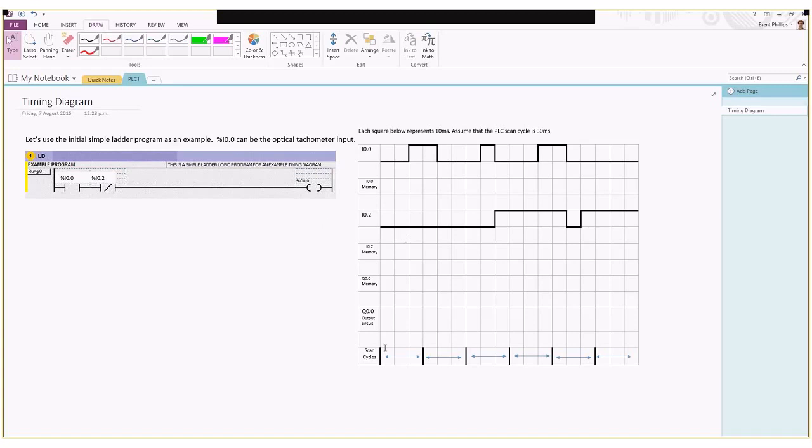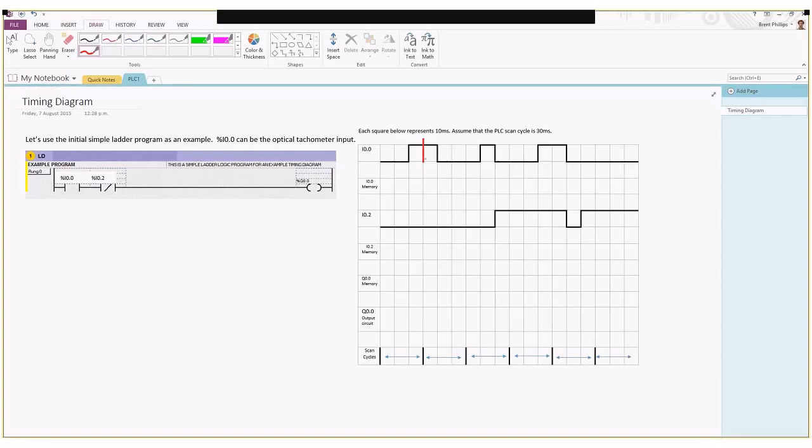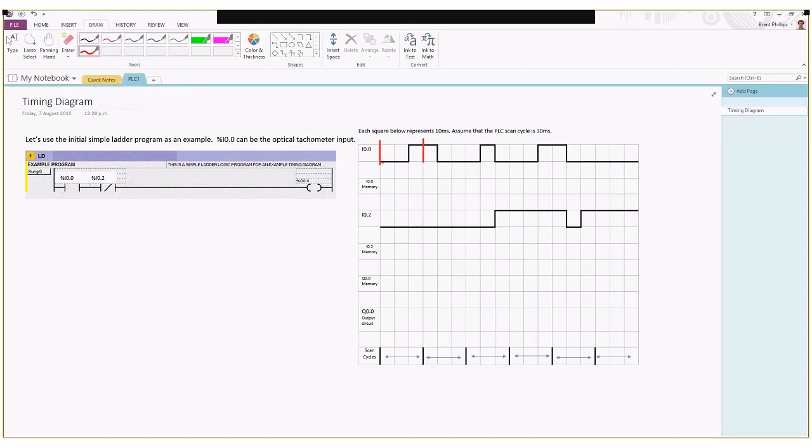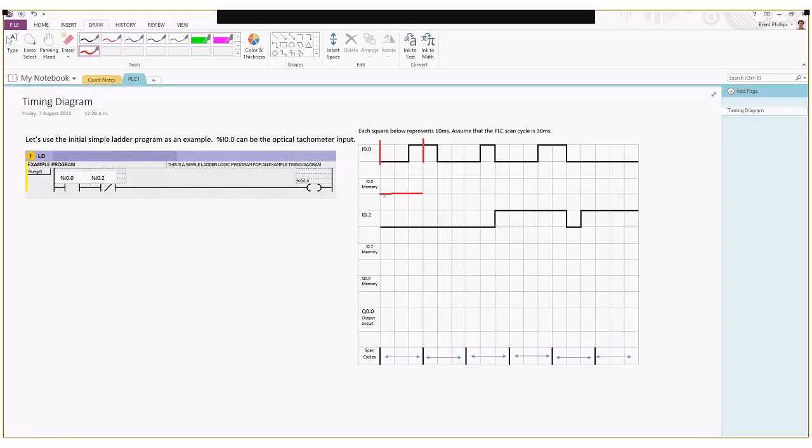At the bottom of the diagram here we've got the marks for when our scan cycle starts and ends. I'm going to start off with drawing and follow that line from where our scan cycle ends up and line that up with my input, because at this point in time and at the very start, this is when the PLC takes the value of the physical input and puts it into the memory. We can see for all of this first scan cycle the value is going to be at the zero state because it gets saved into the PLC memory in this first position right at the start.